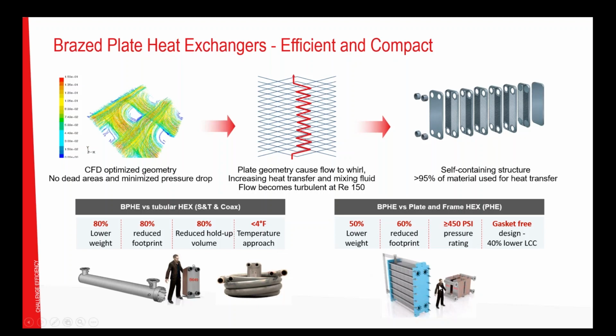If we compare the two plate type heat exchangers, the plate and frame and the brazed plate, since the brazed plate does not need the frame, and the frame is very, very heavy, you will get about a 50% reduction of weight with the brazed plate compared to a plate and frame. We will also have about 60% reduced footprint, not because of the heat exchanger itself, but because the plate and frame has gaskets, and over the lifetime of this product, you have to open it up. You have to be able to get the plates out to change the gaskets. So you have to have a lot of service area. And you don't need that with the brazed plate.